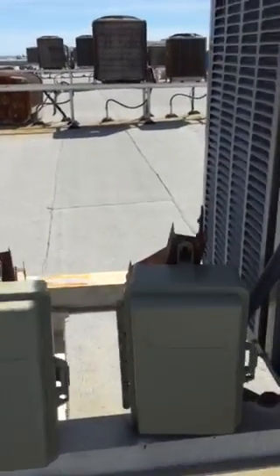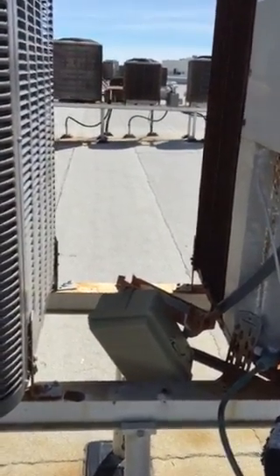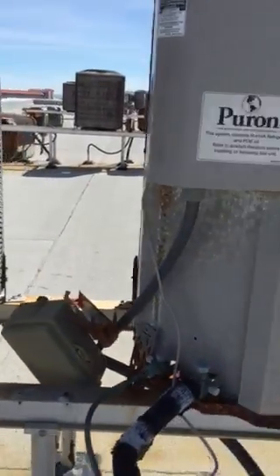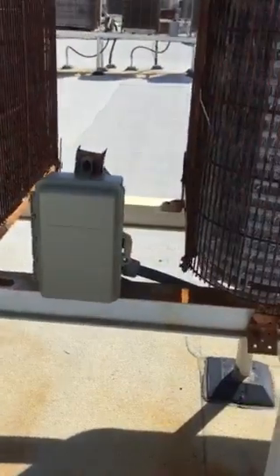403 — this box is kind of loose and is going to need to be replaced. 502, the box is going to need to be remounted. And then 502 down at the bottom is really rusting away.